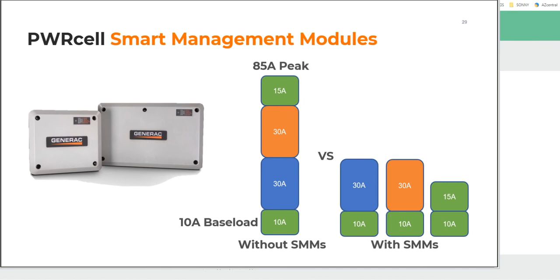But if you integrate automatic switching that enables you to load shed in case you're reaching inverter overload, then you can absolutely put 85 amps of load into that panel and power them one at a time. Fundamentally, this allows us to give a code compliant solution to deliver power to more loads than we'd be able to without this smart management and load switching.